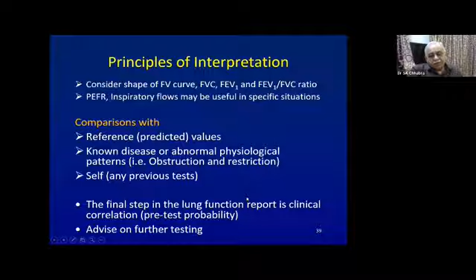Now, what about the normal values? For all biological measurements, we need a normal value to say whether the patient's measured values are in the normal range or they are abnormal. In lung function testing, we do not have fixed normal values. The normal values vary with the patient's race, that is ethnic variation, height, age, and gender. So all persons will have different normal, or what are known as predicted, values based on these parameters. That is why these parameters are entered when spirometry is done. And we match the patient's values with a population which has similar parameters. This is obtained from prediction equations.